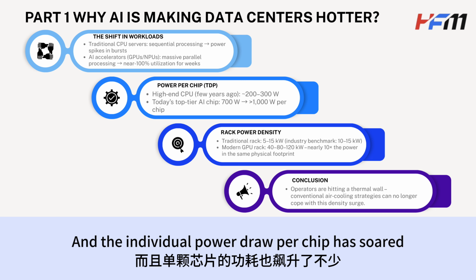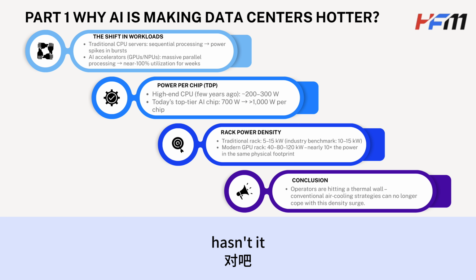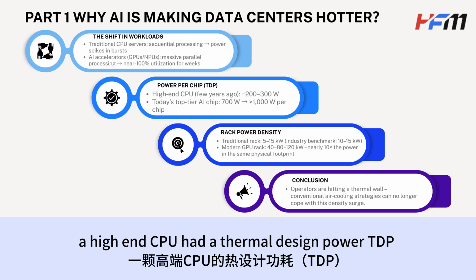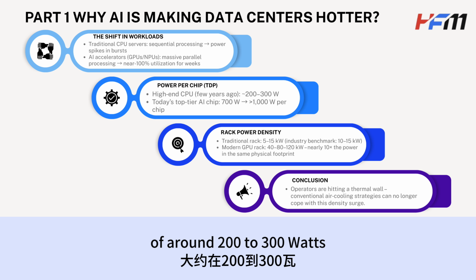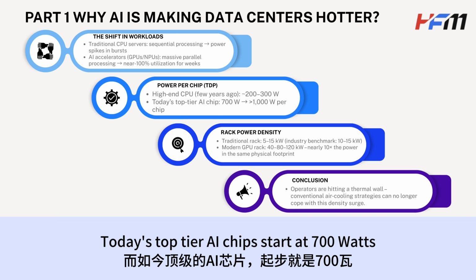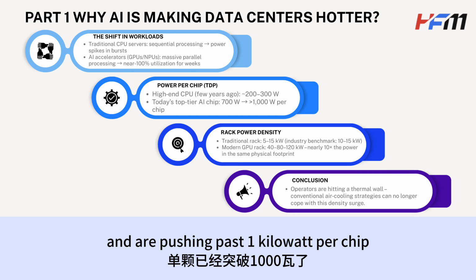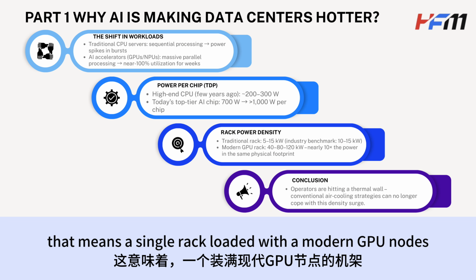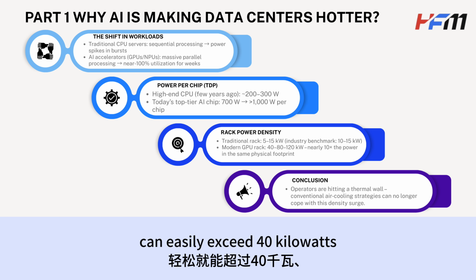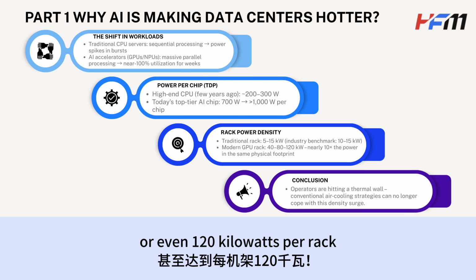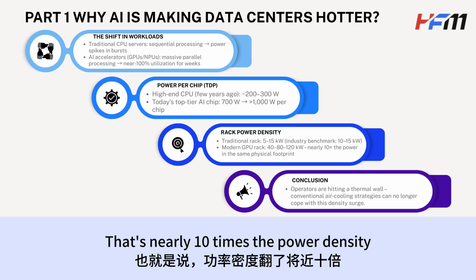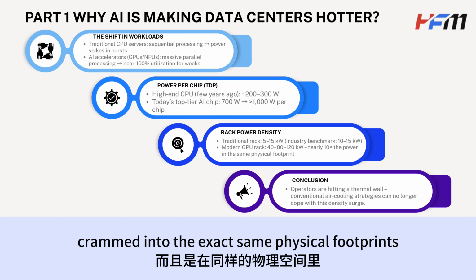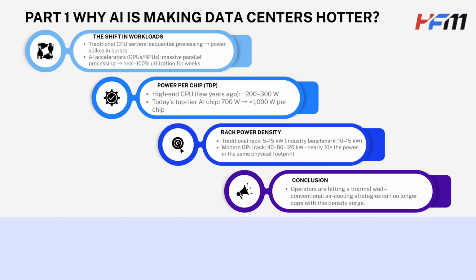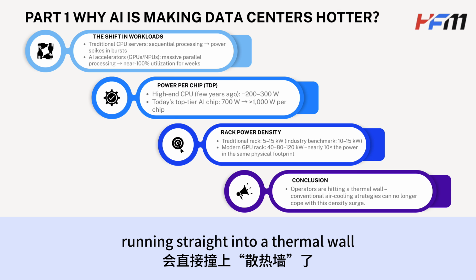And the individual power draw per chip has soared, hasn't it? Yes, dramatically. A few years ago, a high-end CPU had a thermal design power, TDP, of around 200 to 300 watts. Today's top-tier AI chips start at 700 watts and are pushing past 1 kilowatt per chip. That means a single rack loaded with modern GPU nodes can easily exceed 40 kilowatts, 80 kilowatts, or even 120 kilowatts per rack. That's nearly 10 times the power density crammed into the exact same physical footprint. It's no wonder operators are running straight into a thermal wall.